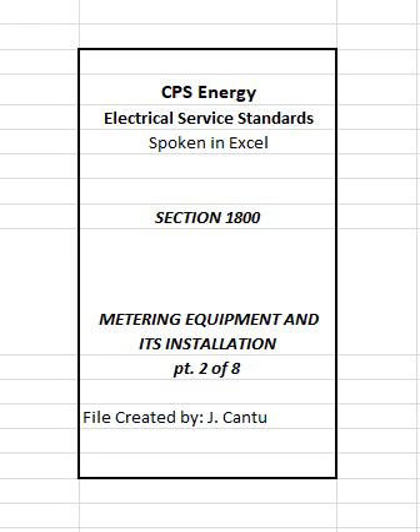F. For overhead primary voltage service, the CT/VTs will be installed on a CPS Energy-owned primary meter pole. Refer to section 1200. G. For underground primary voltage service, the CT/VTs may be located within customer's switchgear or switchboard, or they may be located within an outdoor primary metering pad mount cabinet. CPS Energy will furnish this enclosure at customer's expense. Refer to section 1300.